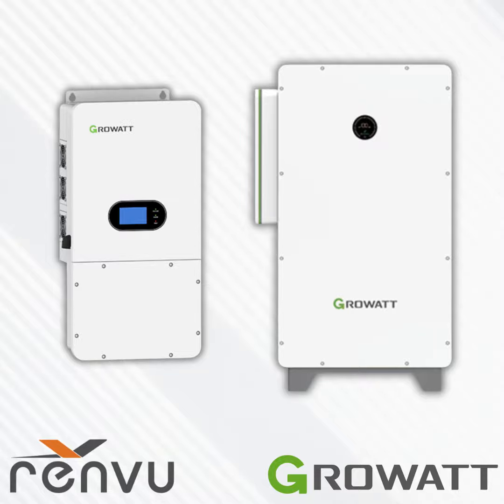The batteries have a max charge and discharge rate of C/2. So for the APX 200 kilowatt hour unit, the max charge and discharge is 100 kilowatts. And then when you go down to the smaller ones like the 86, then the max is 43.